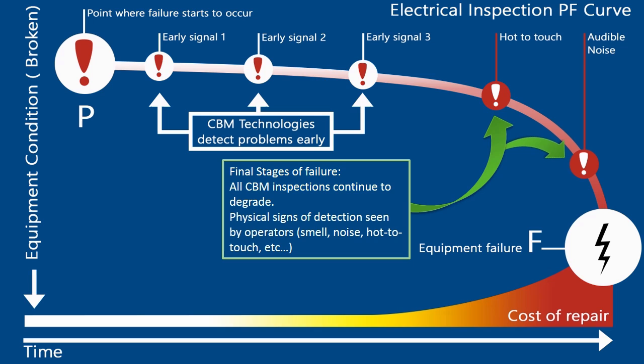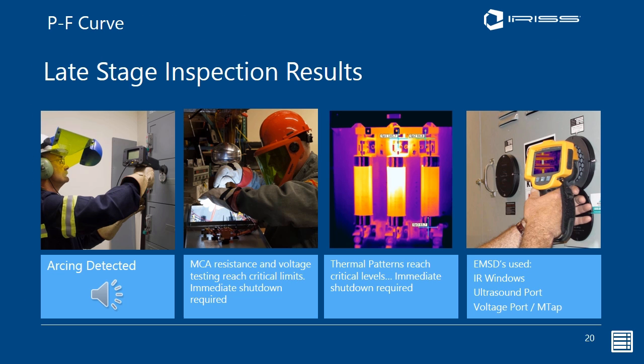We would still start to see arcing. We would see the results from the motor current analysis and thermal imaging increasing again, elevated temperatures, elevated voltage and current readings. So by the time we get to that stage, it's too late. We've spent too much money.